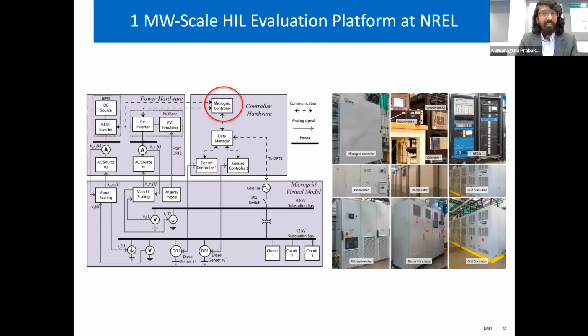This shows some of the hardware setup we have in the lab. We brought in the same microgrid controller and the same diesel generator controllers that exist in the field, and we used RTDSs that model the power system in EMT domain in real time. We have close to a megawatt of power hardware, both on the AC side, using AC grid simulators, and on the DC side, 500 kVA PV emulators and another 500 kVA battery energy storage emulators. We interface this power hardware to our digital real-time simulators, and the controller hardware is interfaced using communication protocols like DNP3 and other digital communications.